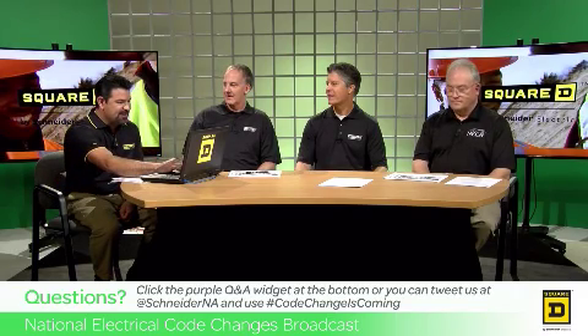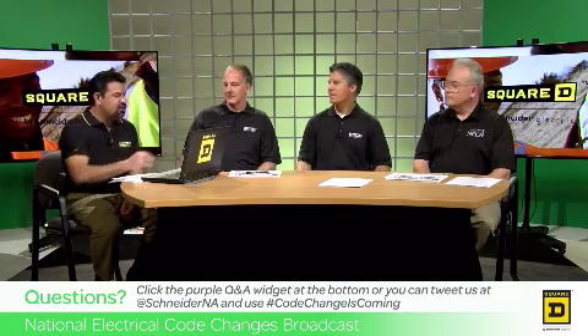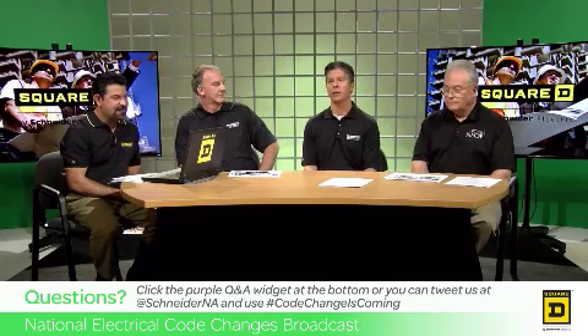Yeah. So the first one that has come in is in section 230.95: can breakers be removed from the gear and tested with current injection and bolted back into the gear? And the answer to that is no. The ground fault protection equipment will include neutral sensors that are not associated with the breaker. You think of a breaker that is a 3-phase, 4-wire application typically. The neutral sensor is part of that ground fault protection equipment, and so all of that busing system needs to be in place. And if you go through the testing that the manufacturers provide, there's both load and no load testing and line and load side testing for that ground fault protection of equipment. So the bottom line is you'll need to follow the manufacturer's instructions, but it will be with the breakers installed in the equipment. Great, thank you, Chad.